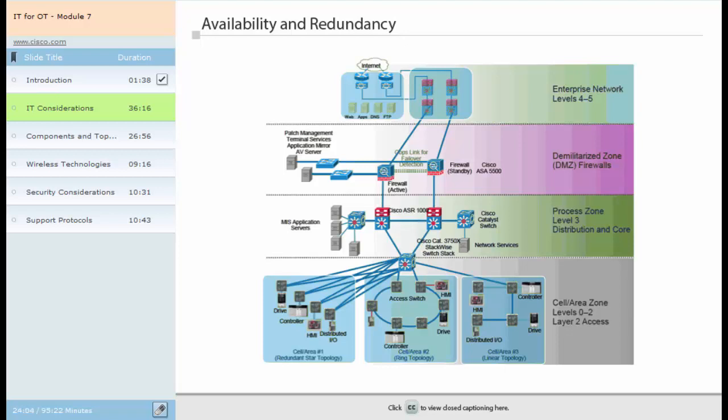For critical applications, it is recommended to use a dual channel redundant architecture on both the operation and machine control units, with two processors each — a master and slave processor. Each processor performs the same functions and compares results periodically. If any inconsistencies or failures are detected, an alert is declared and the system stops.